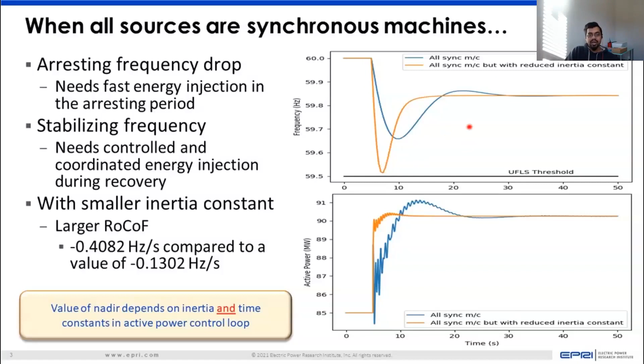Even in a world with synchronous machines, if you have reduced inertia constants, then you naturally see a higher rate of change, but you equally see a faster stabilization, because the time constants involved in the mechanical part of the control system are much smaller due to the smaller inertia constant. So the value of the nadir, as we see in the rest of the talk, depends not only on your inertia constant, but also on the time constants in the mechanical control path or the active power control path. They play an extremely crucial role in deciding how fast you can stabilize your frequency and how you can stay away from the UFLS threshold.